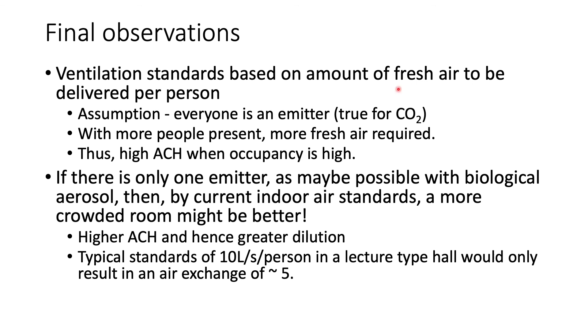The current ventilation standards are based on the amount of fresh air that needs to be delivered on a per person basis. The assumption here is that everyone is an emitter, which is indeed true when we're talking about CO2. The standards call for more fresh air when more people are present. When the occupancy is high, you have high air changes per hour. Because of the scenario where there's only one emitter, which is not unusual when talking about bioaerosol, then by the current indoor air standards, it is paradoxically better to be in a more crowded room. Because in a crowded room, you have a higher air changes per hour, and so you've got greater dilution.